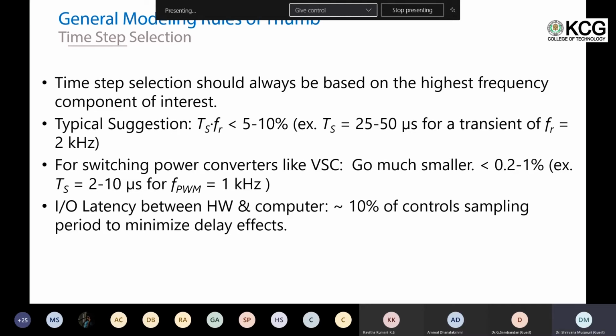It's a known thing, but I wanted to re-emphasize again: the time step selection should always be based on the highest frequency component of interest. For example, if my frequency of interest is let's say 2 kilohertz, I want to effectively capture and understand a 2 kilohertz transient phenomena. Then the suggestion is to take 5% or 10% of that as the sampling time step selection. So for 2 kilohertz, we'll end up with 25 or 50 microseconds to effectively capture that transient.